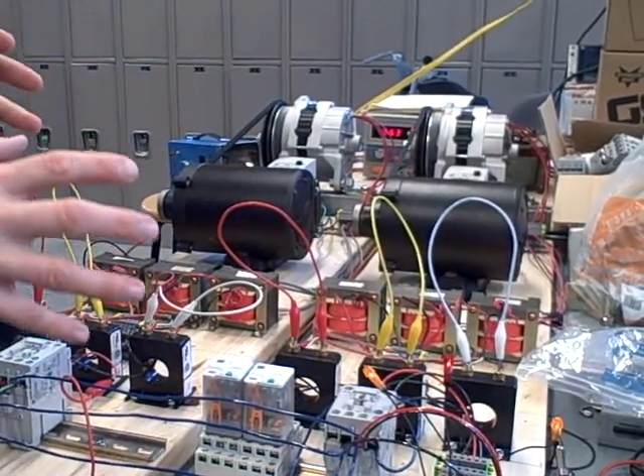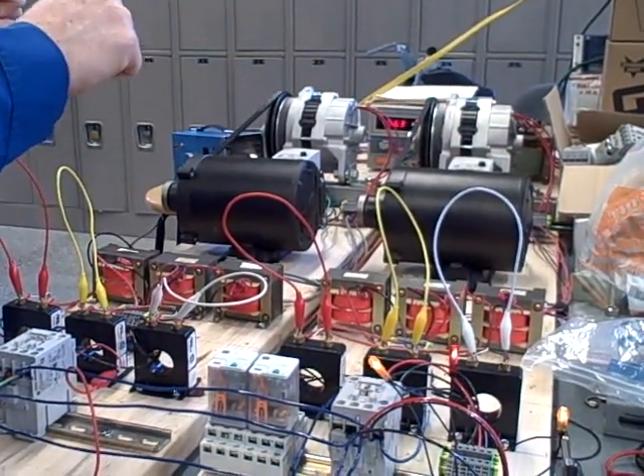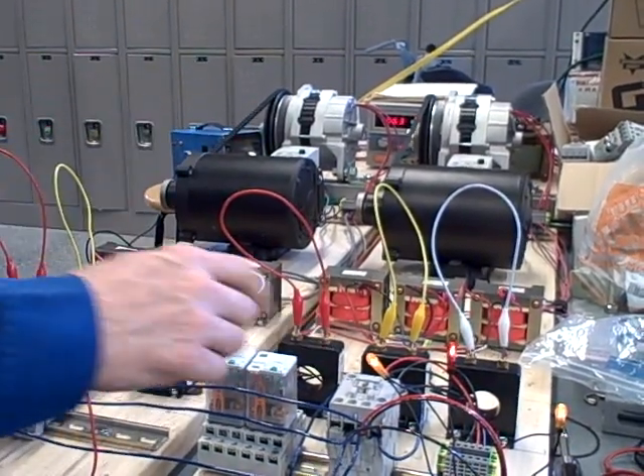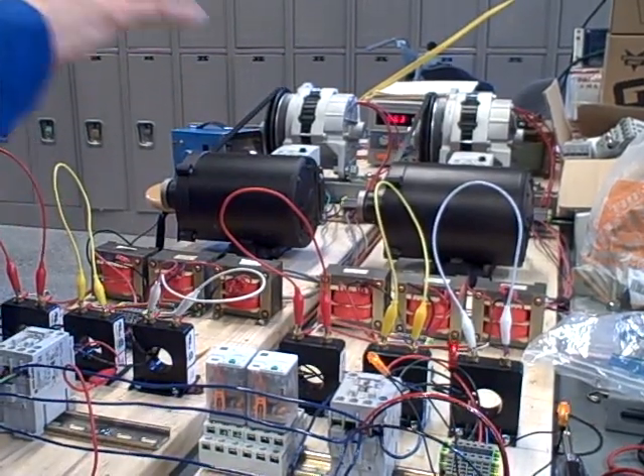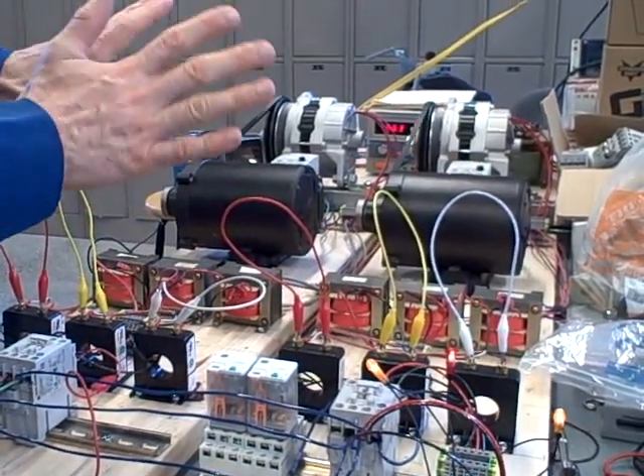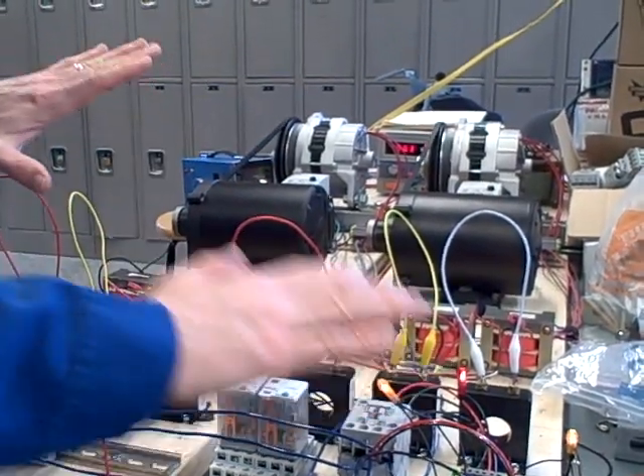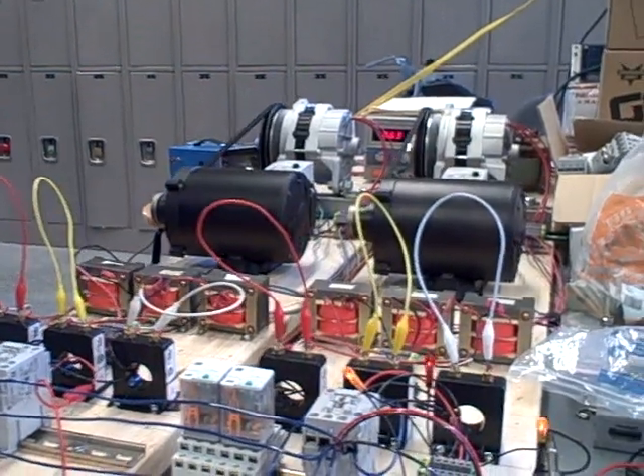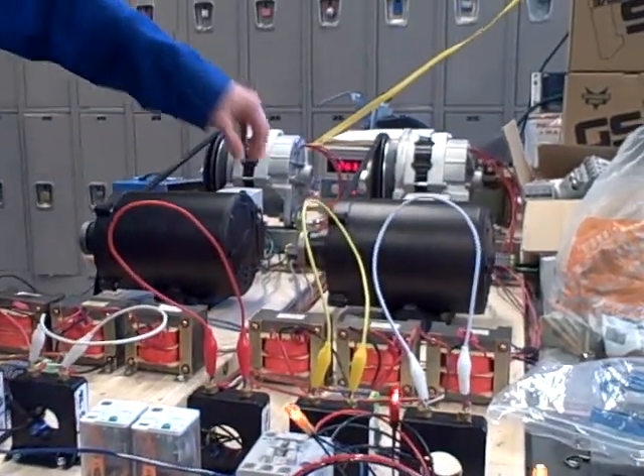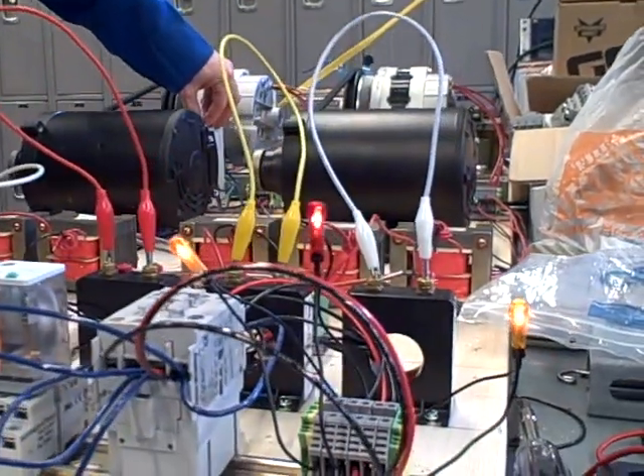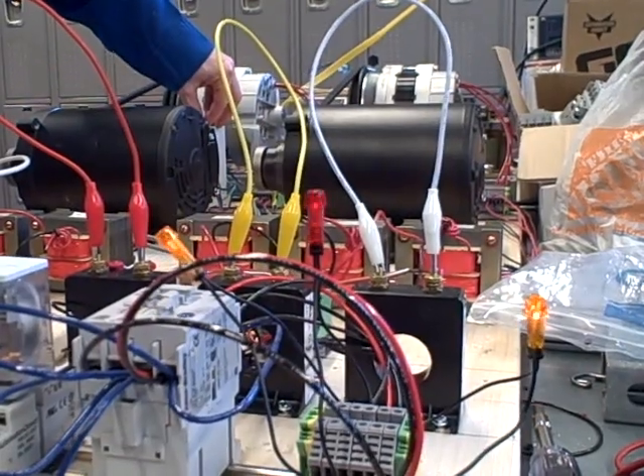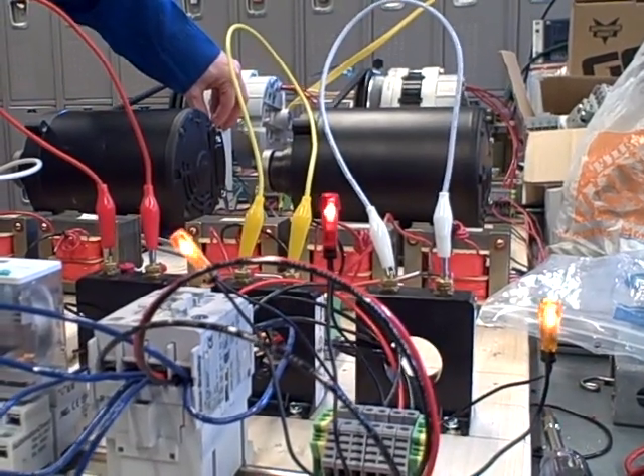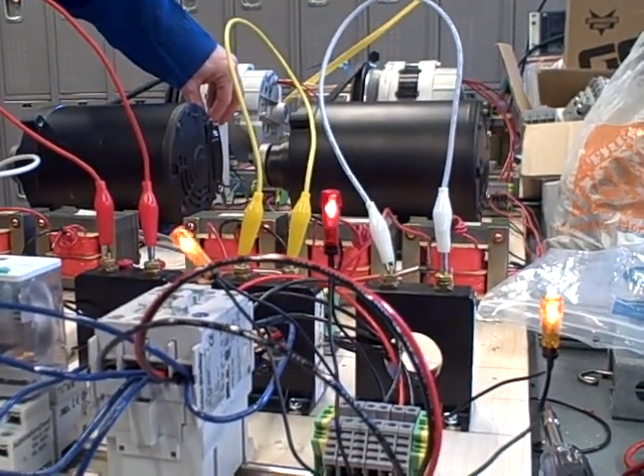So in order to make these suitable for synchronizing together, for closing that breaker and getting them in parallel, I need to get them in phase to the point where these lights are off and are staying off. So watch me as I speed this generator up. I speed up the generator, blinking slower, speed up the generator, blinking slower.